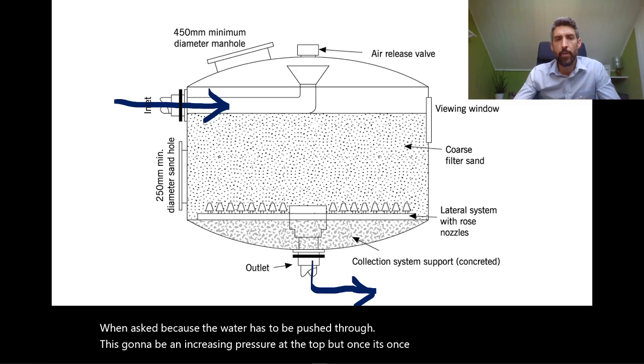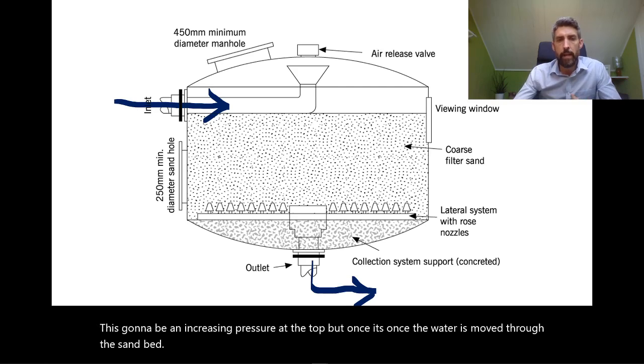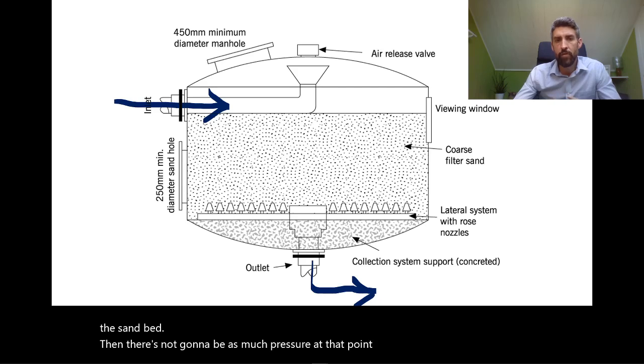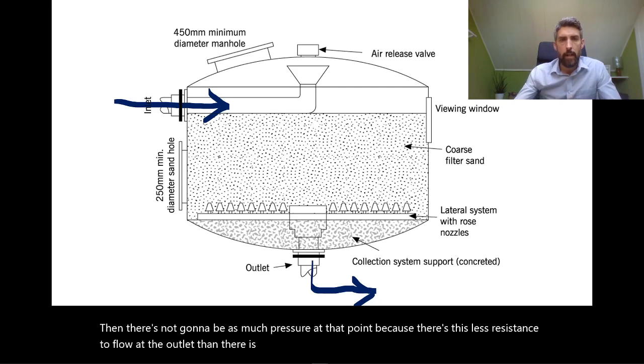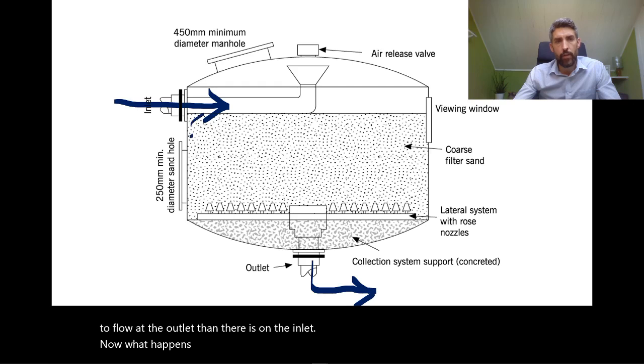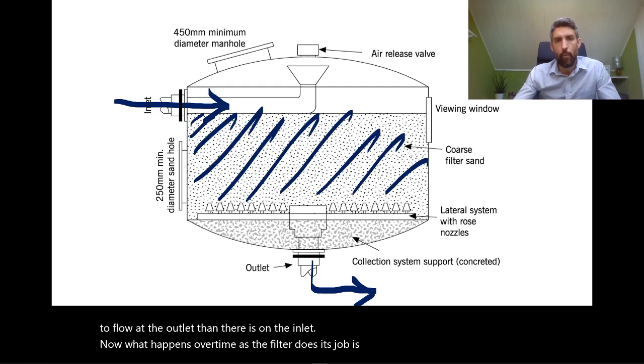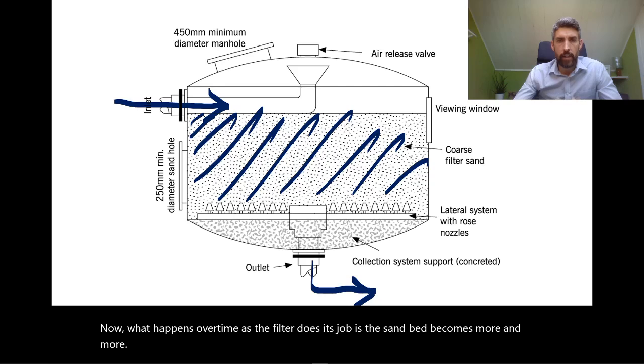Once the water has moved through the sand bed, there's not going to be as much pressure at that point because there's less resistance to flow at the outlet than there is on the inlet. Now what happens over time as the filter does its job is the sand bed becomes more and more saturated with pollution from the swimming pool.